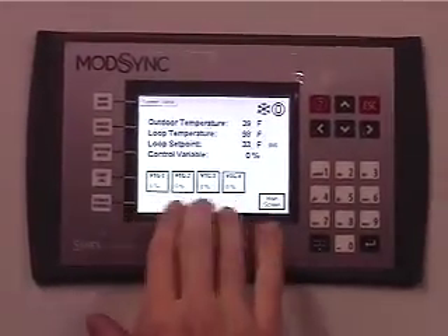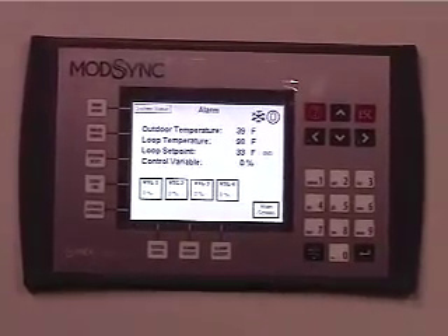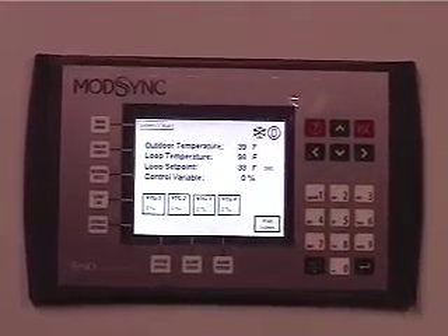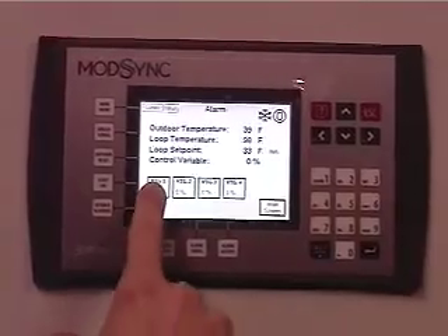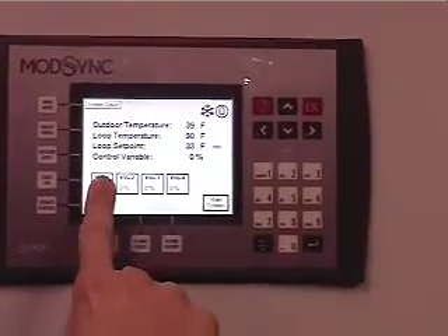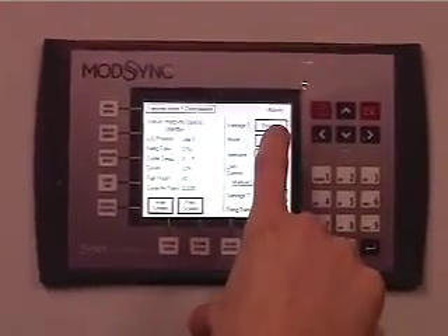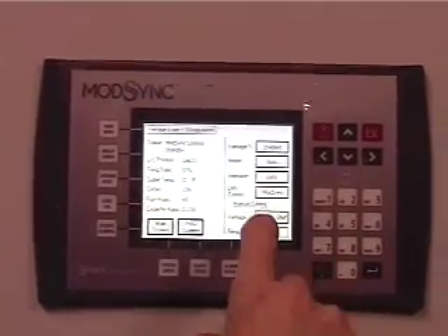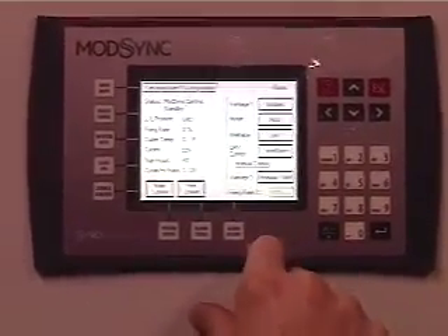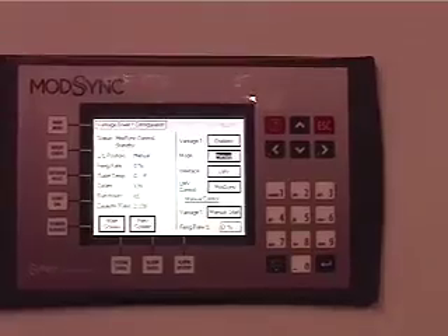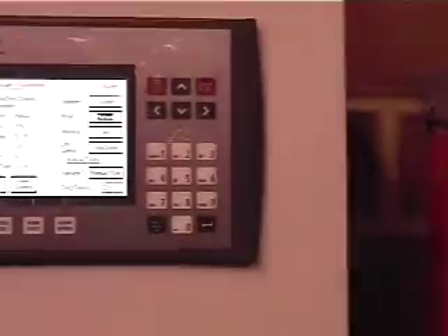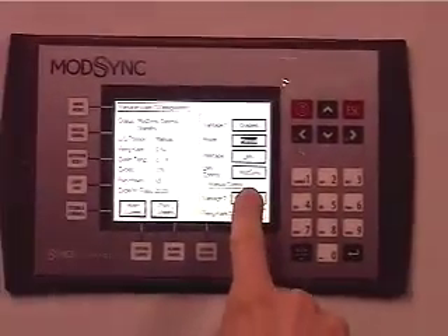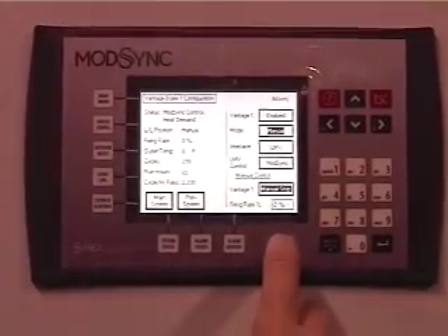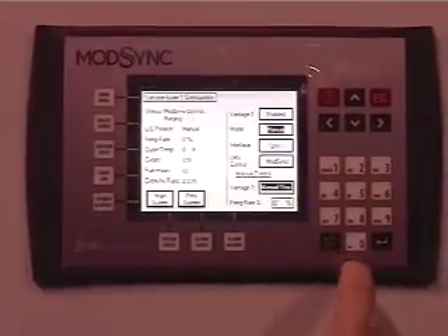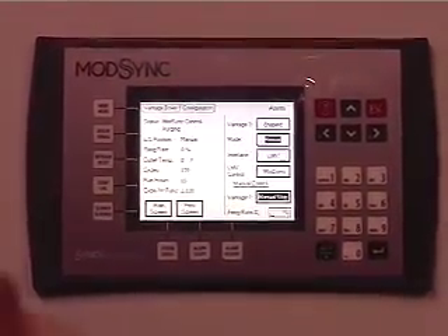Exactly. And then no boiler will go above that 60% level until all 4 are on and firing, and then it will. So you can get into boiler 1, and you can say it's enabled, it's in auto. I believe I can click on the auto and go manual. And you start. And then you can tell it to go to 100% firing.